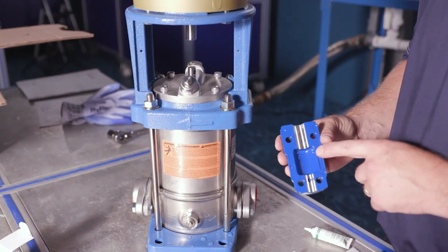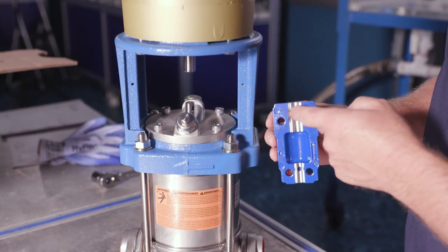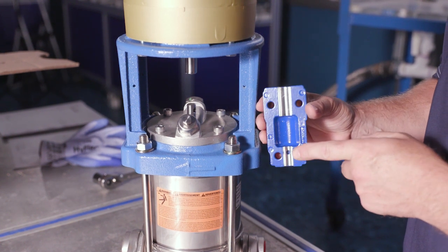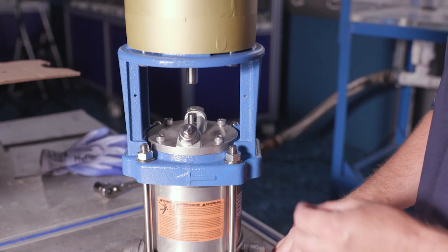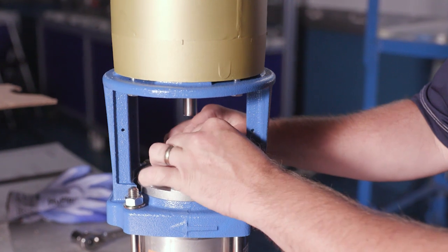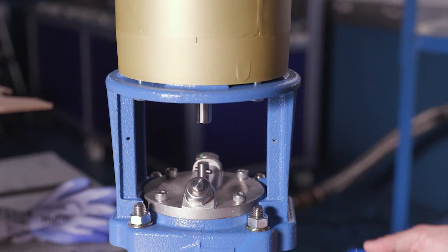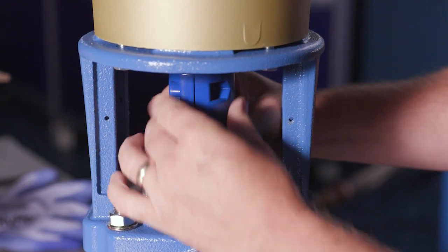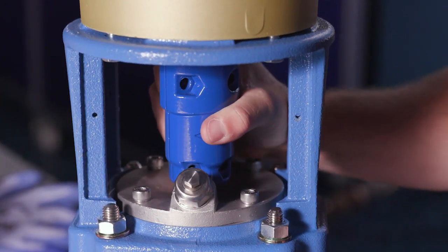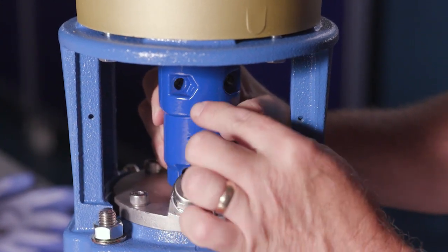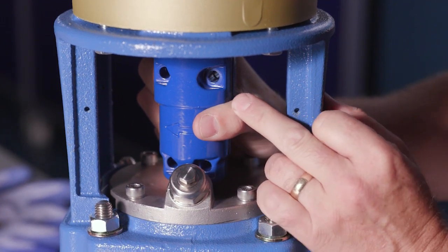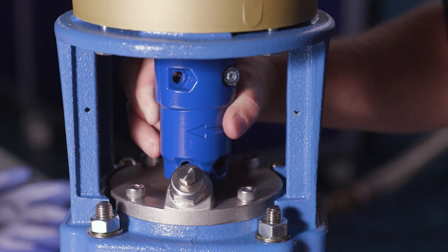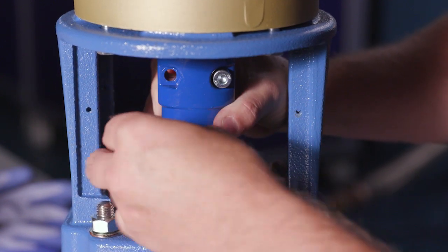Next, we're going to install the coupling. A couple things to keep in mind: the top is a compression fit for the motor shaft and the pump shaft has a pin, so we've got to make sure that we put the pin back in. The other thing that's important about your coupling, we can see where the hex goes in the round section here, where the head of the bolt would go. You can see another round section over here.